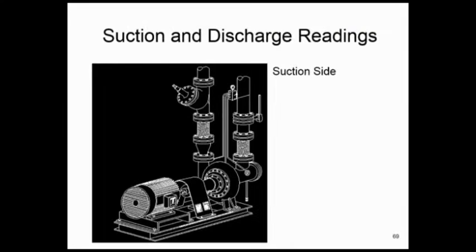So let's go to our pump, and let's look at suction and discharge gauge readings again. I like to take them with the same gauge. I know individual suction and individual discharge gauges are fine. But when I want an accurate differential pressure across my pump, please take that with the same gauge. If you've got two gauges, take it twice. Take them individually with the same gauge because, again, what am I after? I'm after the actual pressure drop. Let's turn it around. Instead of saying pressure drop, I'm after the pressure the pump's generating. I'm really talking about pumping the pressure up here. So what is the actual differential pressure the pump's putting into the system?